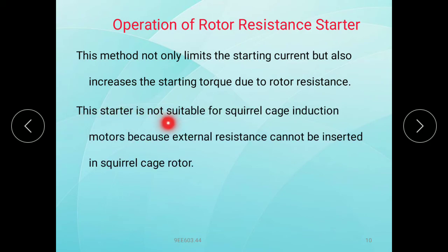This starter is not suitable for squirrel cage induction motor. It is suitable for slip ring motors, because external resistance cannot be inserted in a squirrel cage rotor.